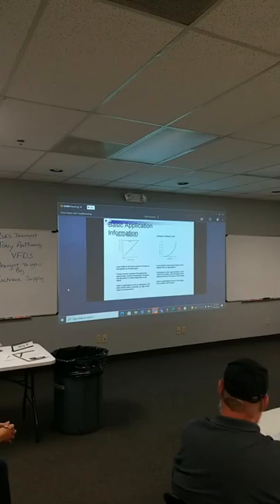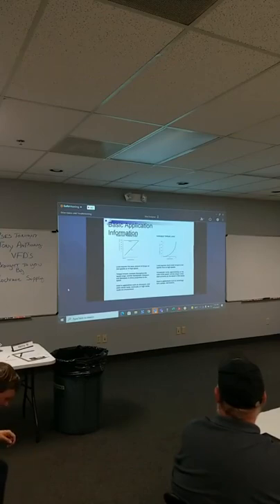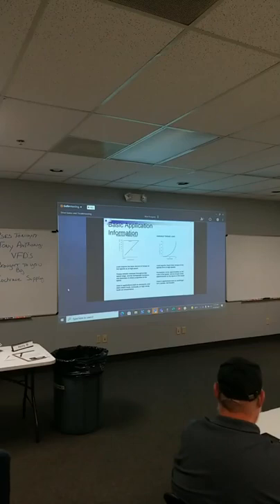So we put a bypass unit, which is a cross-line starter, right there with the drive. You can pull the drive out, repair it, run the motor across the line, get the drive repaired, put it back in, and start saving money again. Nowadays, drives are so reliable and systems are designed not to be run at 60 hertz anymore, so you really don't need the bypass unit, even though we see them all the time. But it's the energy savings that drives that, and it's only on the pump or fan because of those variable torque curves.